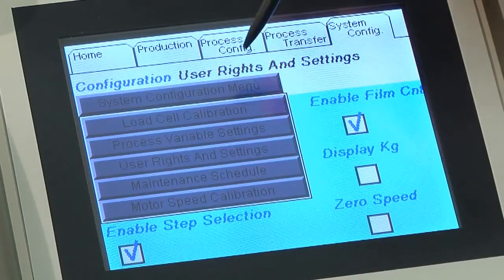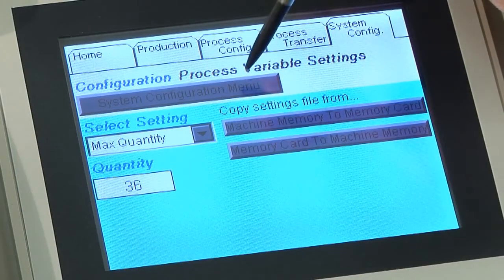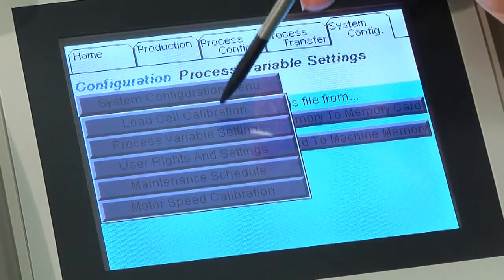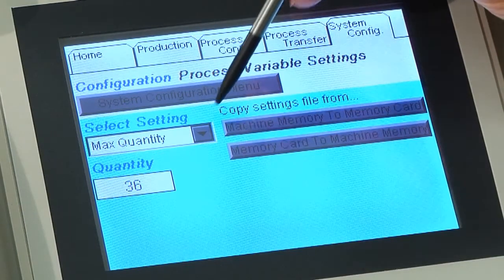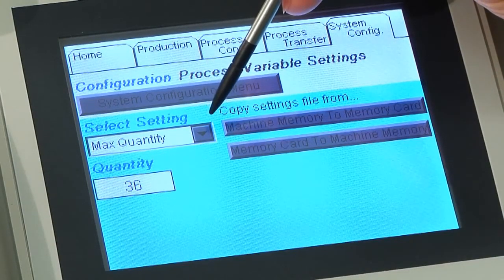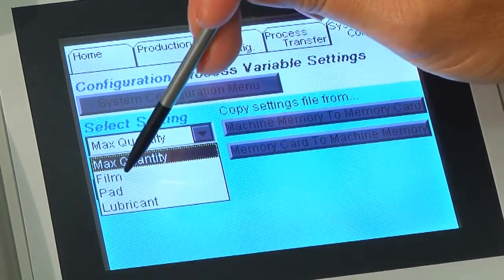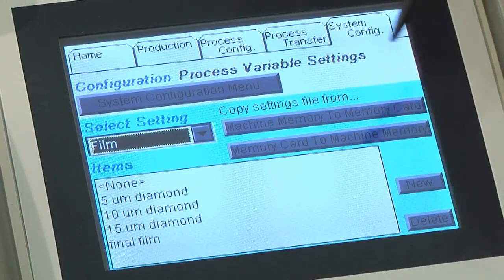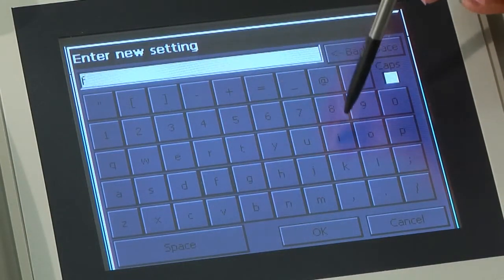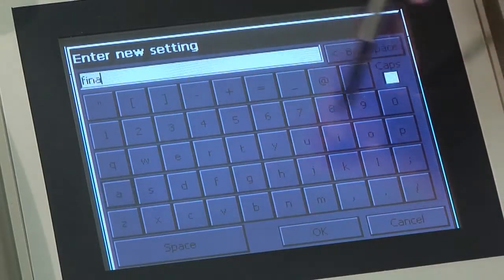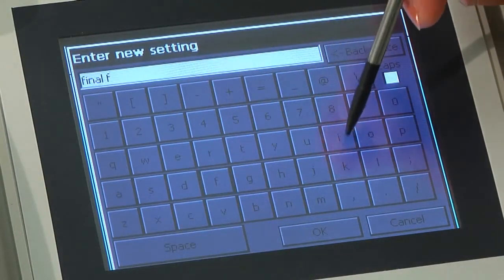Next, click on the process variable settings. Select the system configuration tab, then process variable settings in the configuration box using the down arrow. Select film in the select setting box. Touch the New button to access the keypad and type in a film name for your polishing process. The film name can be up to 32 characters in length. Select OK. Repeat these steps for all films used in your polishing processes.